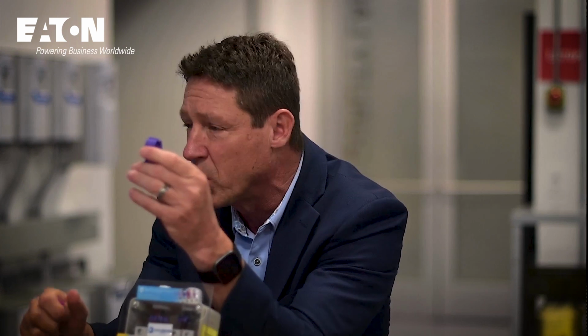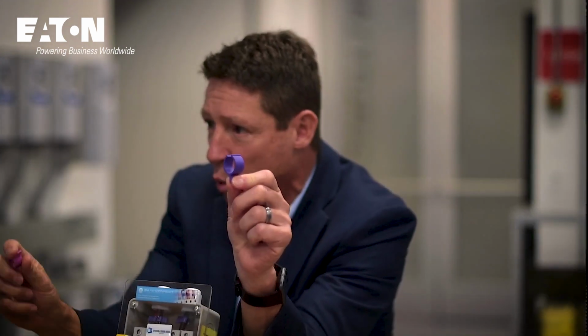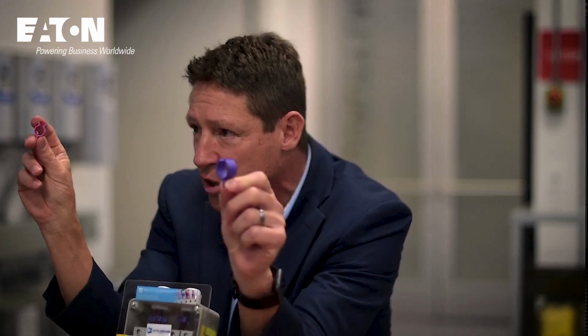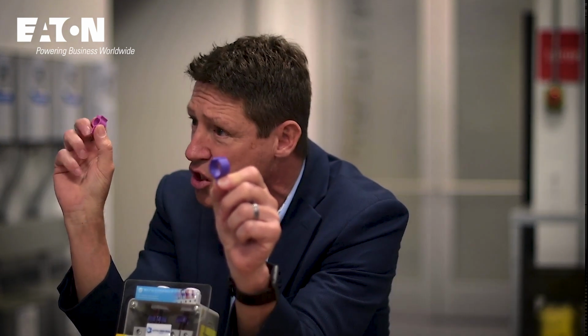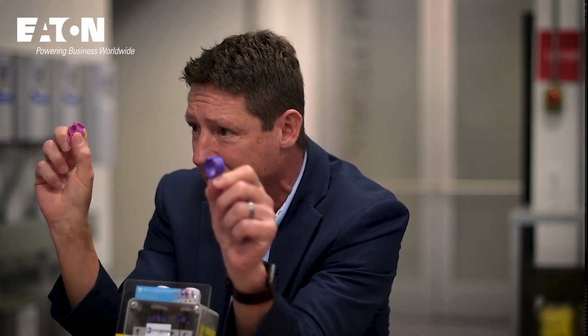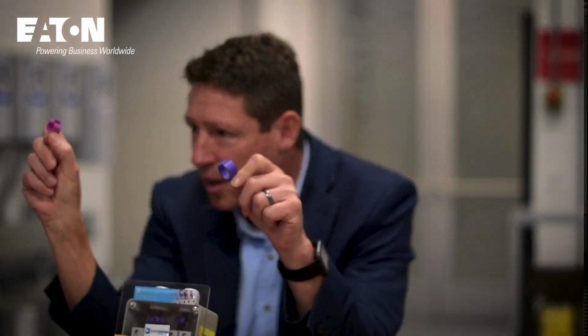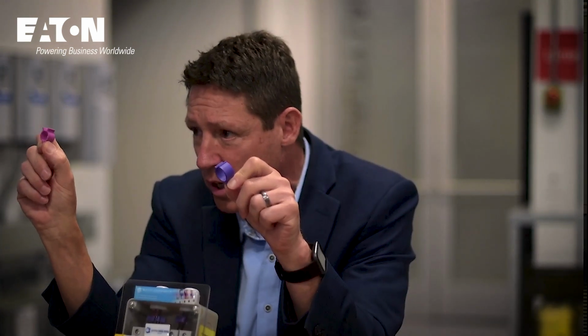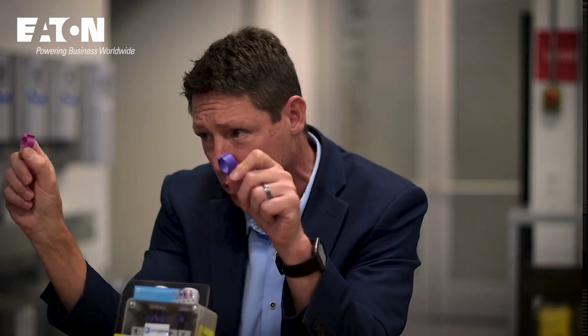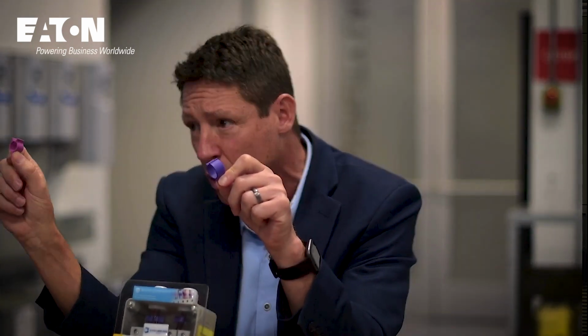We talk about thermography requirements once a year. So what happens when you're not doing thermography and your cable's heating up? That's the purple clip that goes on the cable. Once it hits a temperature of 70 degrees Celsius, this is just a visual indicator that, outside of thermography, the cable is heating up. It turns pink.